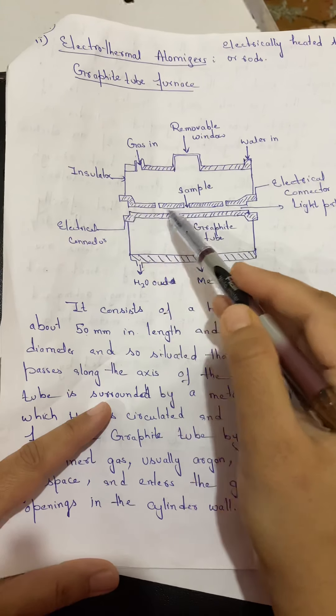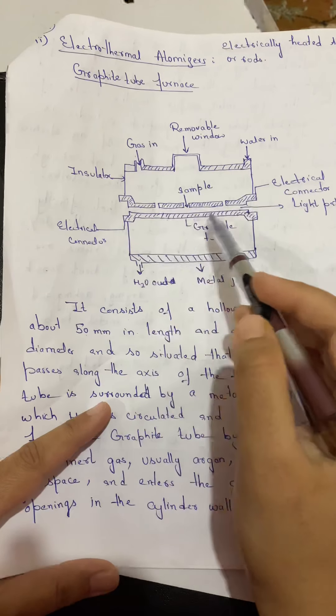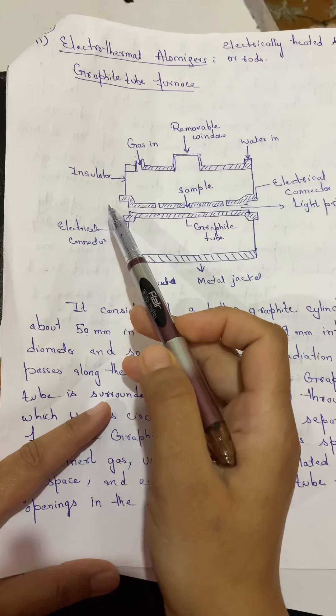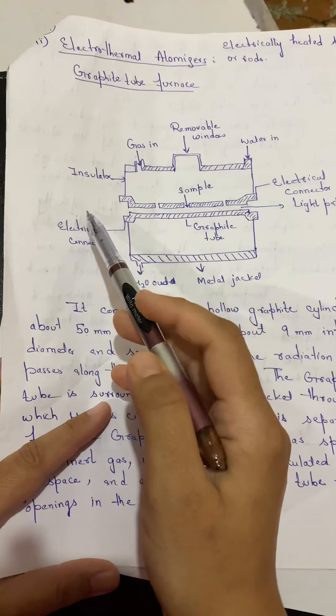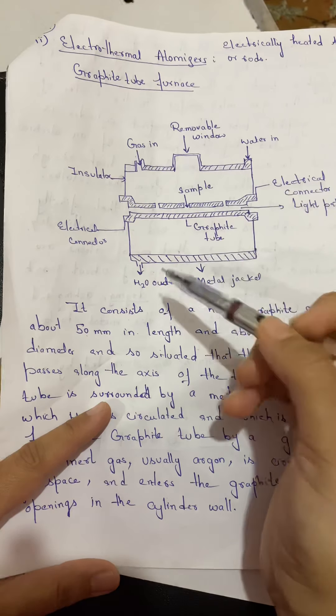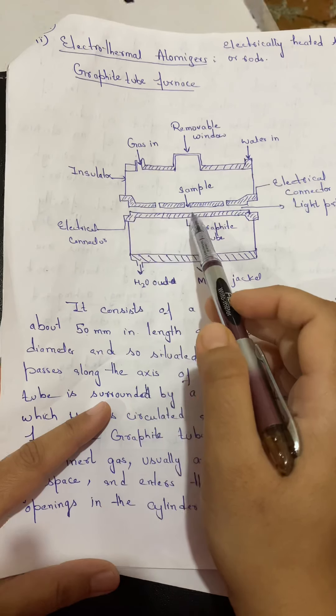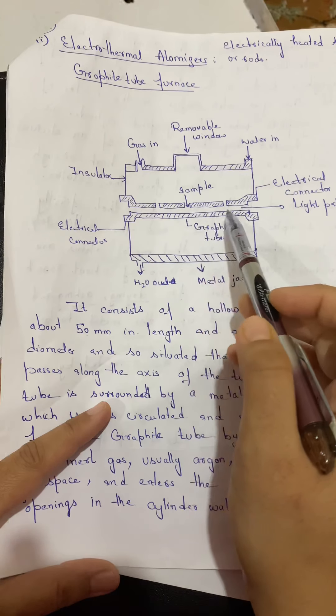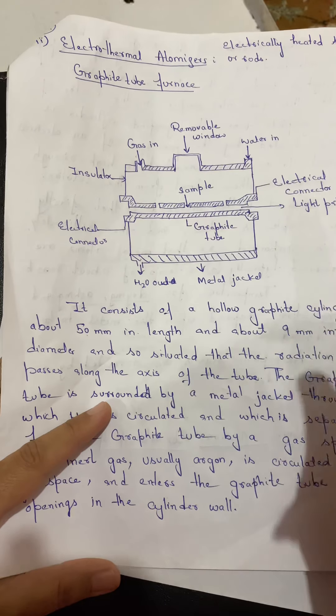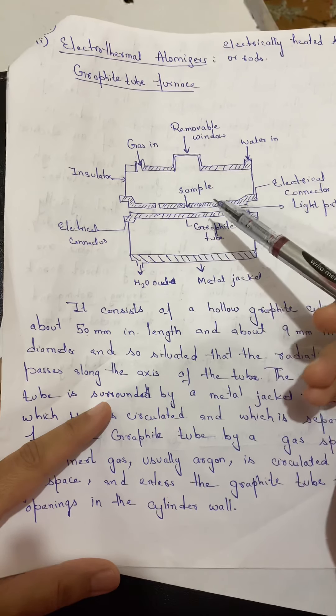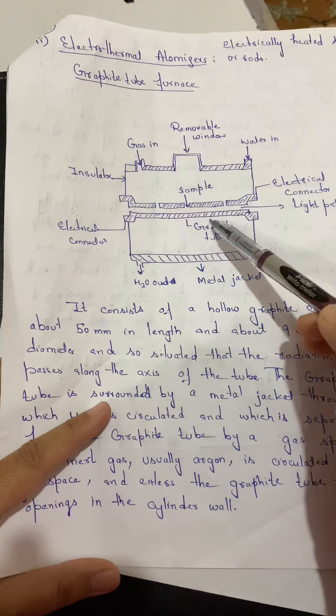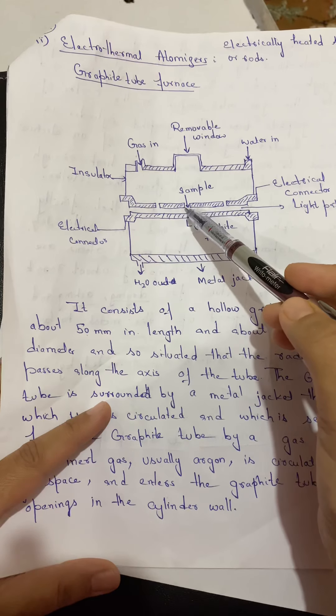The graphite tube has two windows on both sides, forming the optical path through which light passes. We have a hollow cathode lamp which produces radiation of our desired wavelengths. The light passes through the sample in the tube and goes on to the monochromator, detector, and readout devices.